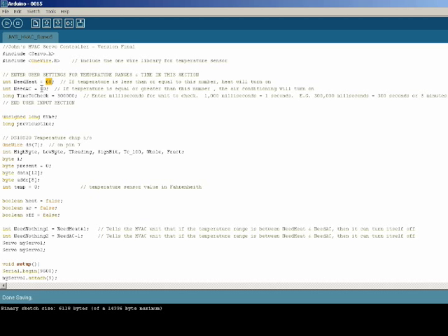Need AC equals 80. That means if the temperature probe reads that the room is 80 degrees or hotter, it will turn the air conditioning on. When it reads the temperature, and if it finds that it's in between these two, it will turn the unit off.